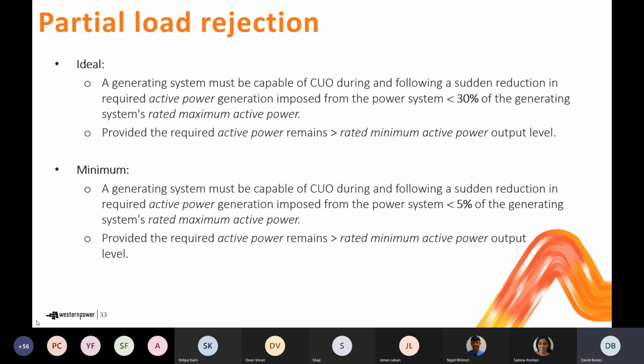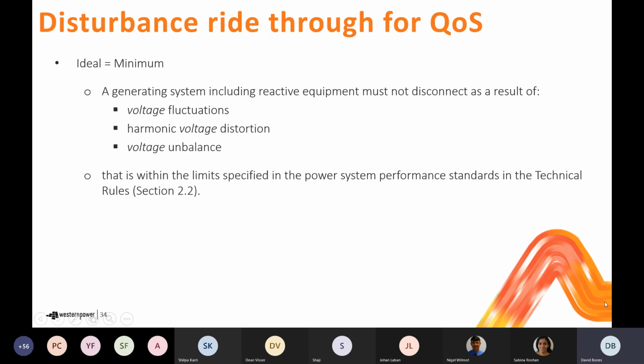So I think that's fairly straightforward, that requirement. And you can see there the difference between the ideal and minimum performance standard. The last of the disturbance ride-through requirements relates back to quality of supply. And what it's requiring is that generating systems do not disconnect, provided the voltage fluctuations, harmonic distortion and voltage imbalance remain within the limits specified in the power system performance standards defined in section 2.2 of the technical rules.